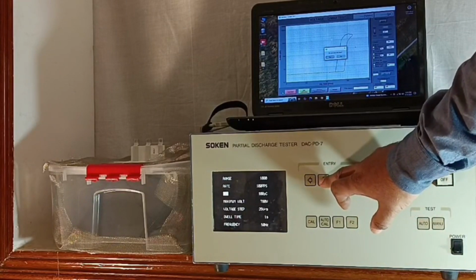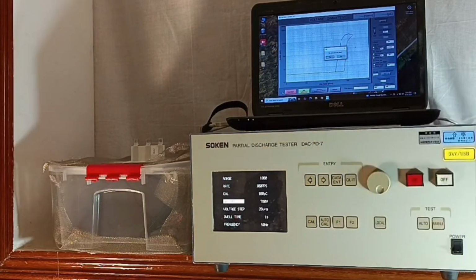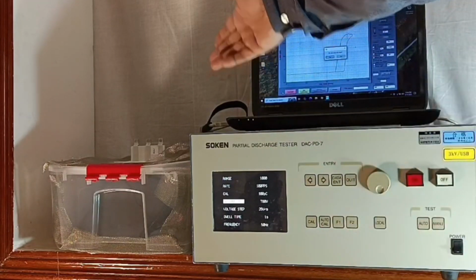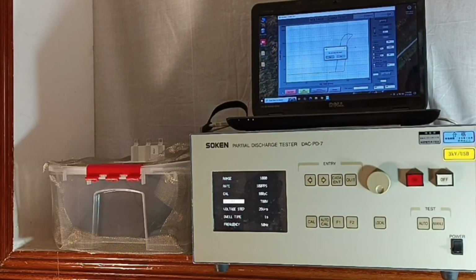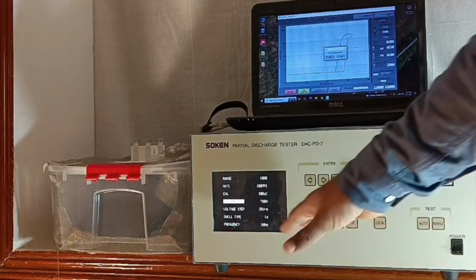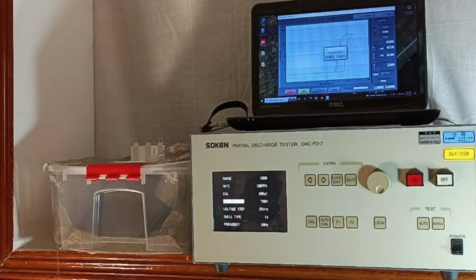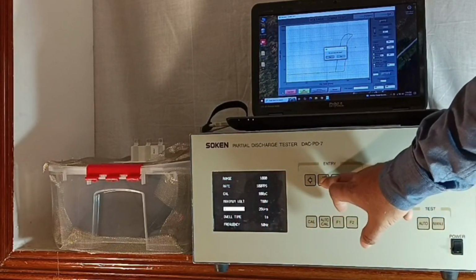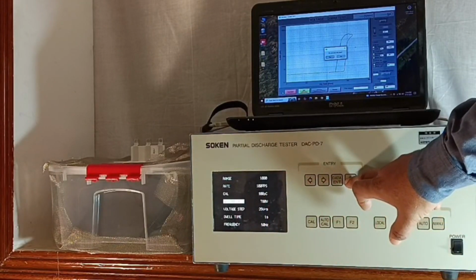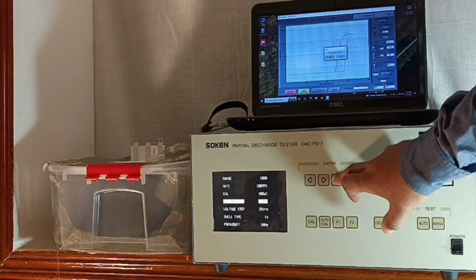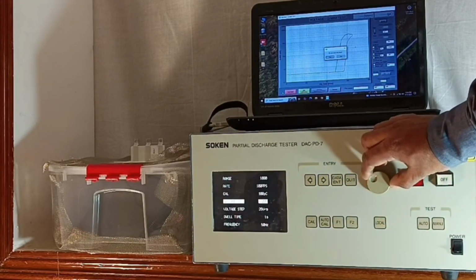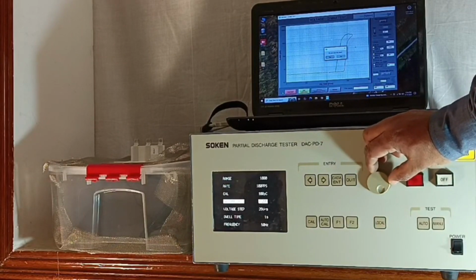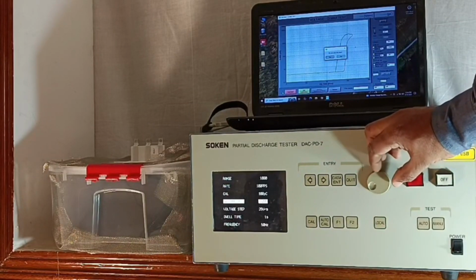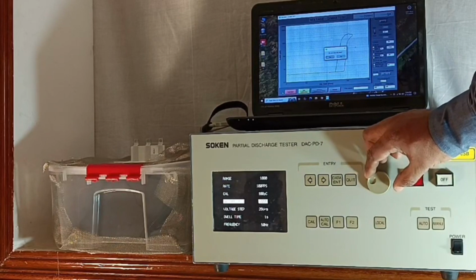Threshold voltage, maximum voltage we want to go. We had set up 700 volts because we had a record of that earlier itself, which was going approximately 600 volts. So we had kept, for a safety reason, 700 volts. That you can change using the knob here. You can go up to 3000 volts in this particular model.